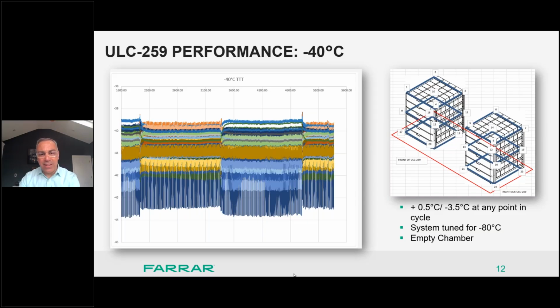And what you'll see here also is that the unit was calibrated for use at -80, and so the mean temperature is around -41 instead of -40. And you'll see that by that brown sweep in the middle. So during cooldown cycles, points in this chamber can hit -43.5 or so, but for the most part, the freezer maintains very close to the set point. So let's dig into our material handling options next.